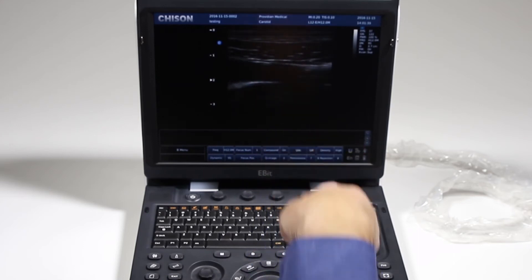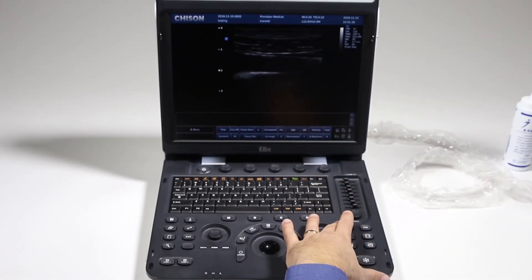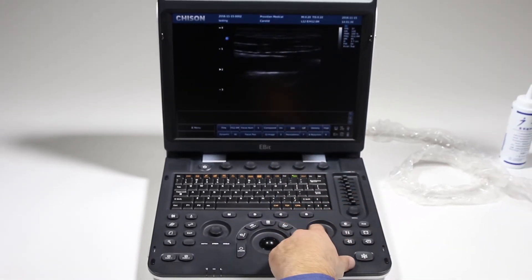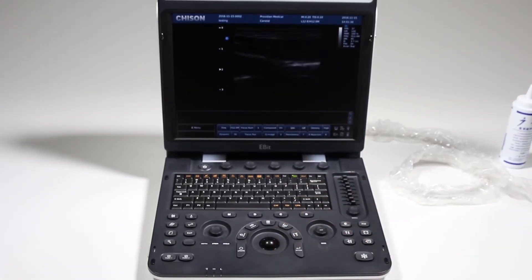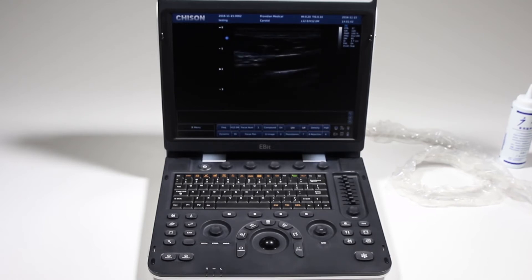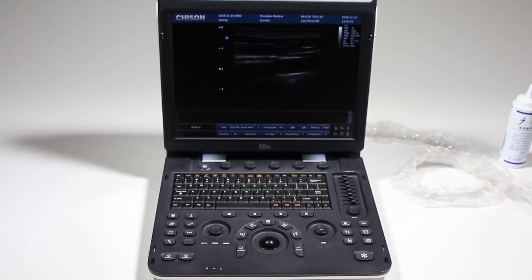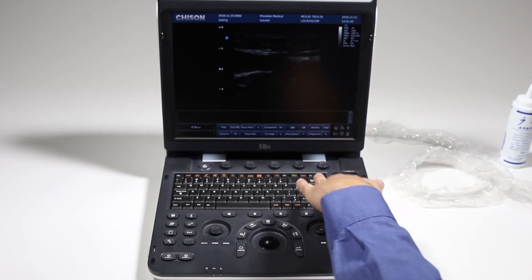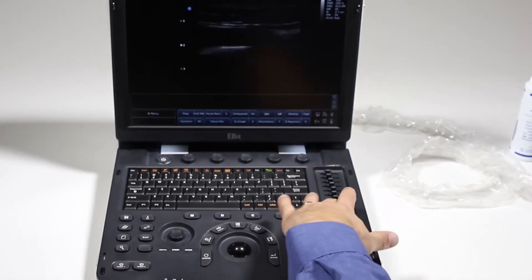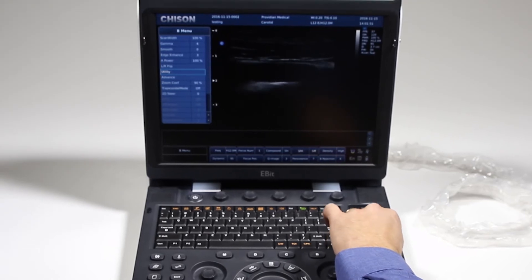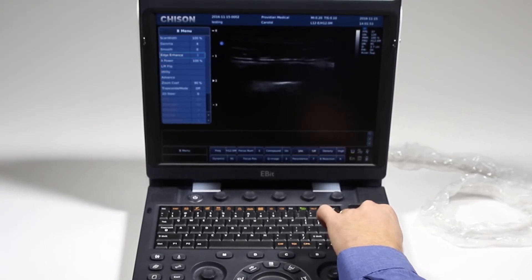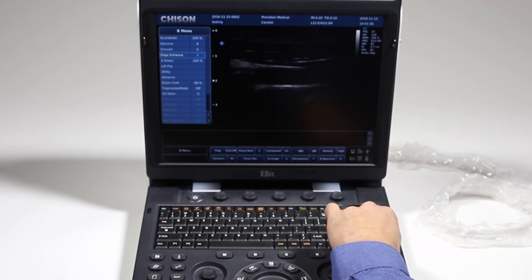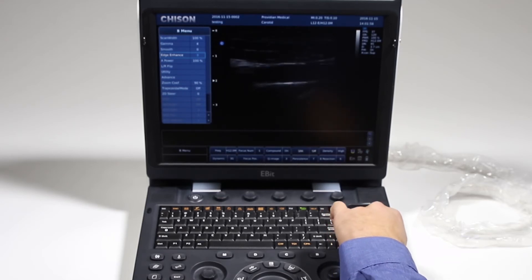Compound imaging also makes a big difference, but you can also play with the auto image optimization. I'm not a huge fan of that. There's not a lot of systems where the image optimization works extremely well, but it's always worth a shot instead of having to play with a lot of different functions. You can also check the edge enhancement feature here and that often helps sharpen up the image and smooth it out.